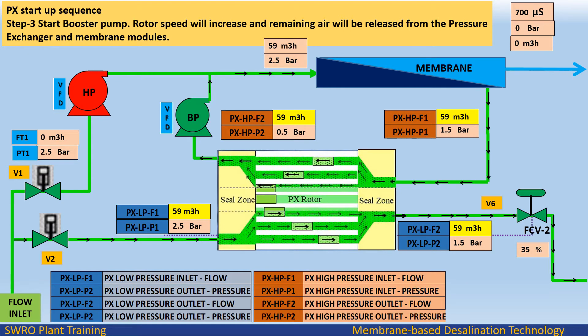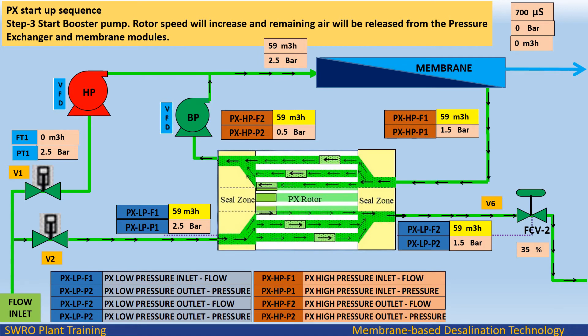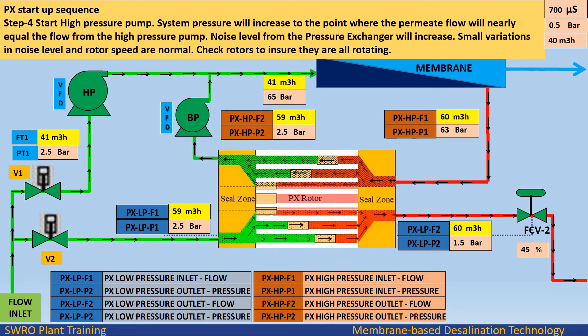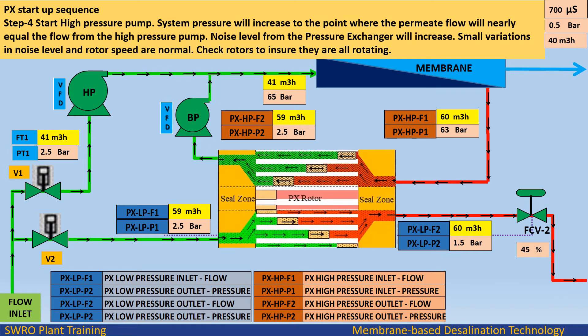Rotor speed will increase and remaining air will be released from the pressure exchanger and membrane modules. PX startup sequence, step 4: start the high-pressure pump. System pressure will increase to the point where the permeate flow will nearly equal the flow from the high-pressure pump. Noise level from the pressure exchanger will increase; small variations in noise level and rotor speed are normal.